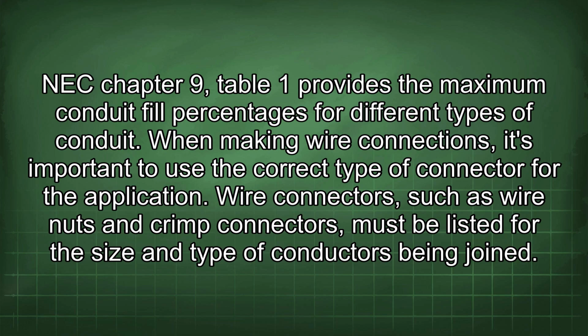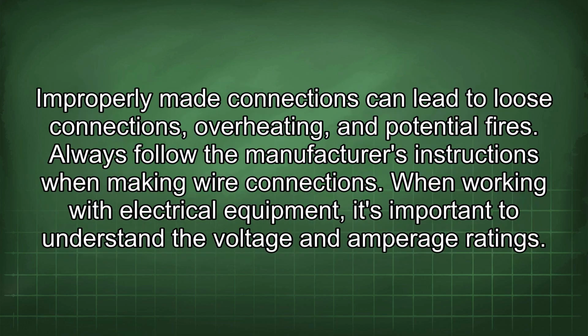When making wire connections, it's important to use the correct type of connector for the application. Wire connectors, such as wire nuts and crimp connectors, must be listed for the size and type of conductors being joined. Improperly made connections can lead to loose connections, overheating, and potential fires. Always follow the manufacturer's instructions when making wire connections.